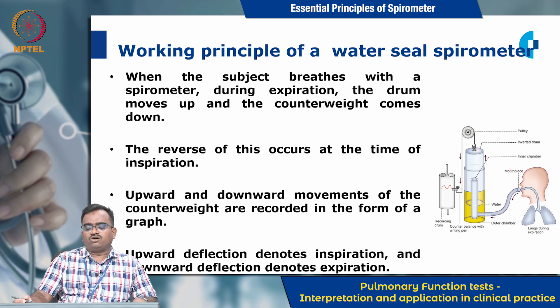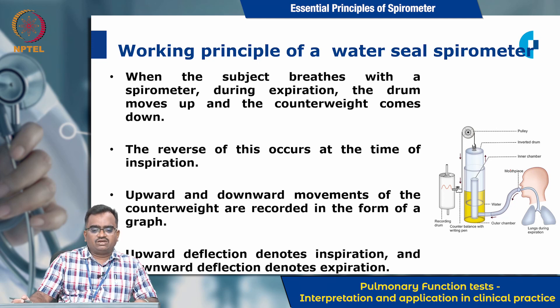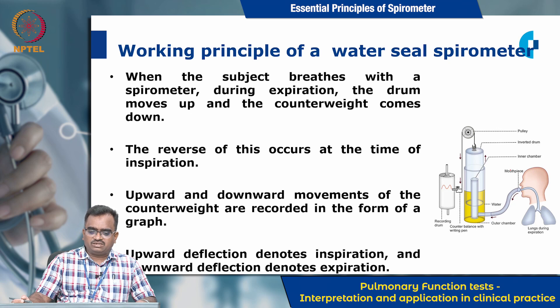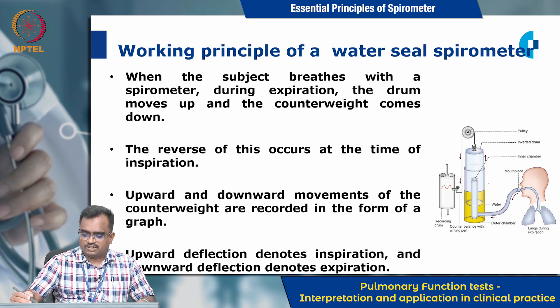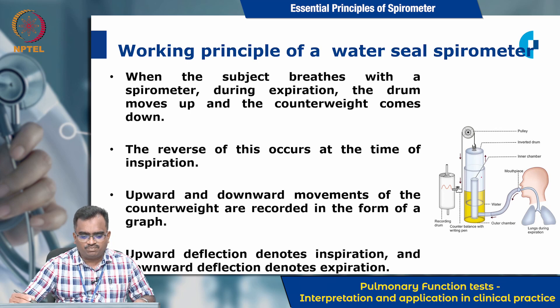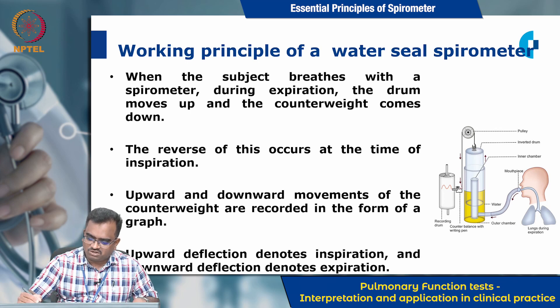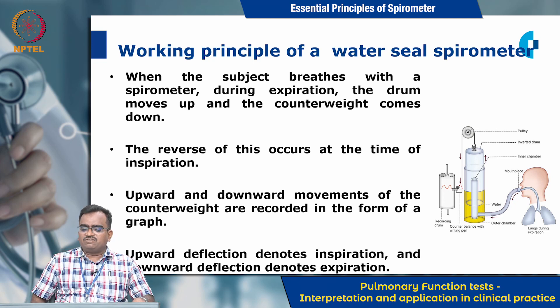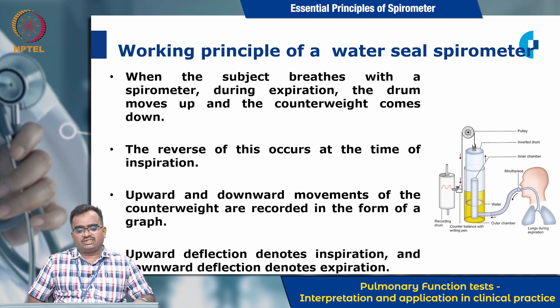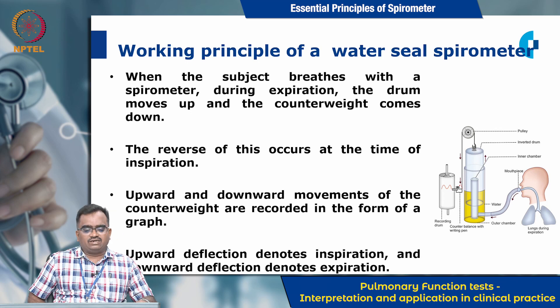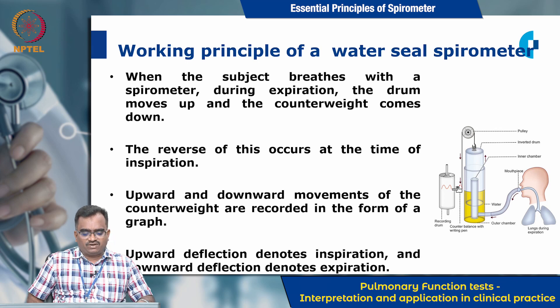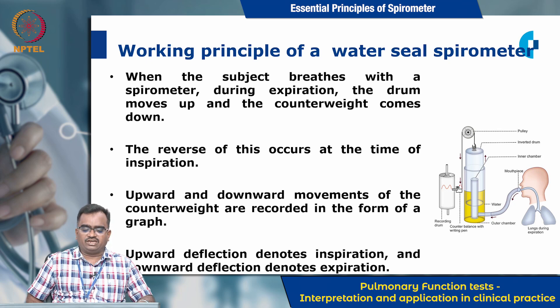Working principle of the water seal spirometer: when the subject breathes with the spirometer, during expiration the drum moves up and the counterweight comes down. The reverse occurs at the time of inspiration. The upward and downward movement of the counterweight are recorded in the form of a graph. Upward deflection denotes inspiration and downward deflection denotes expiration.